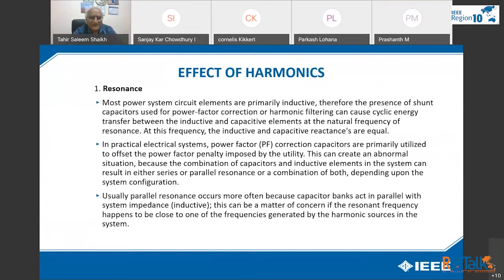In practical electrical systems, power factor correction capacitors are primarily utilized to offset the power factor penalty imposed by the utility. In Pakistan, it is 0.9. This can create an abnormal situation because the combination of the capacitors and inductive elements in the system can result in either series or parallel resonance, or a combination of both, depending upon the system configuration. Usually, parallel resonance occurs more often because capacitor banks are in parallel with system impedance. Inductive, this can be a matter of concern if the resonant frequency happens to be close to one of the frequencies generated by the harmonic sources in the system.